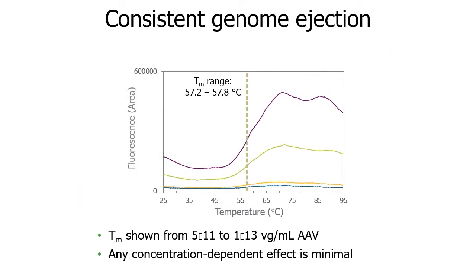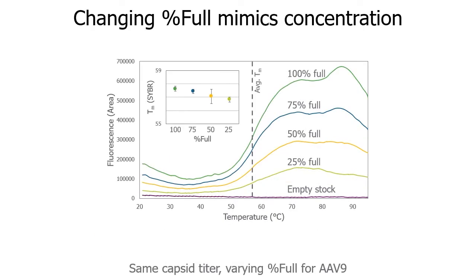Looking at raw fluorescence from 1E13 AAV9 with SYBR Gold, the dye fluorescence appears between about 500 and 650 nm, with the SLS peak at 473 nm. We track the area under the curve for SYBR Gold fluorescence. Starting at 25°C, we get an initial fluorescence read indicating free-floating DNA around capsids. As temperature increases SYBR Gold fluorescence decreases (a temperature-dependent effect), but genome ejection begins around 50°C, reaching a melting temperature around 58°C, continuing until about 75°C where capsid proteins unfold and aggregation occurs. After cooling back to 25°C, a final read shows total DNA released. This assay has a dynamic range from 5×10¹¹ to past 1×10¹⁴ Vg/mL.